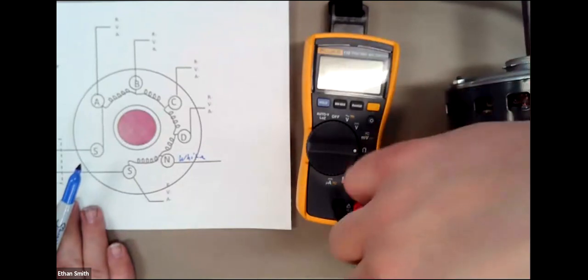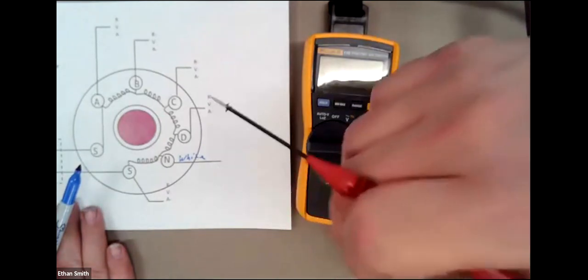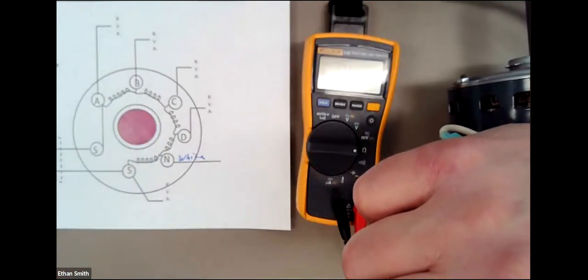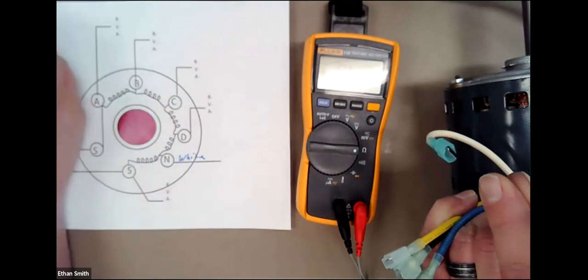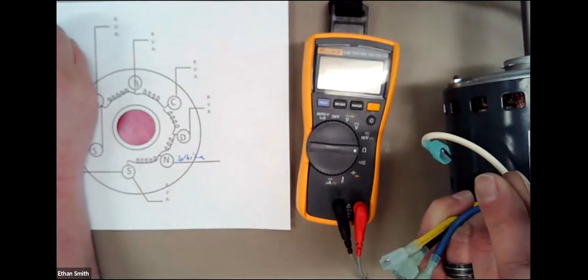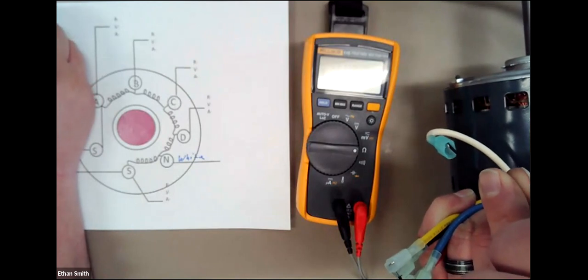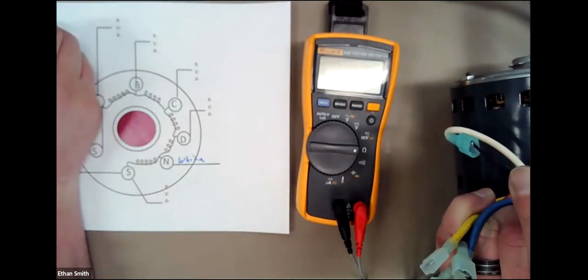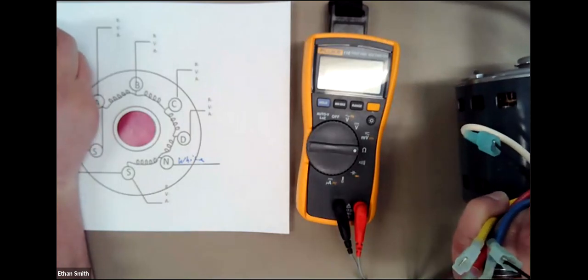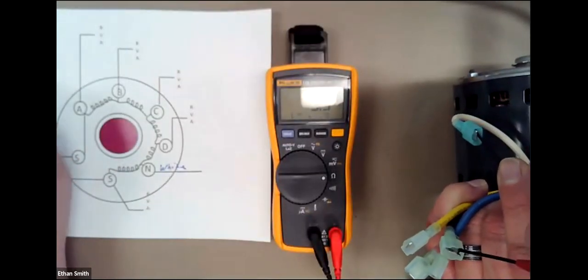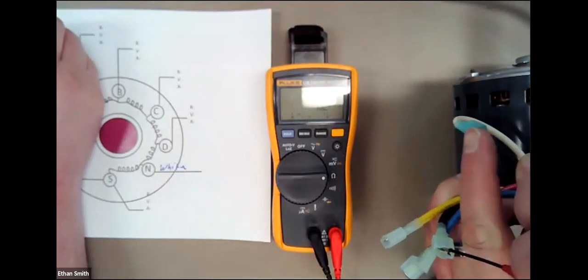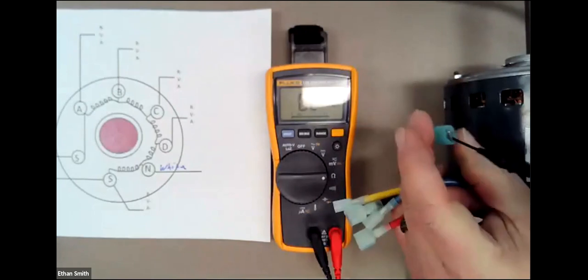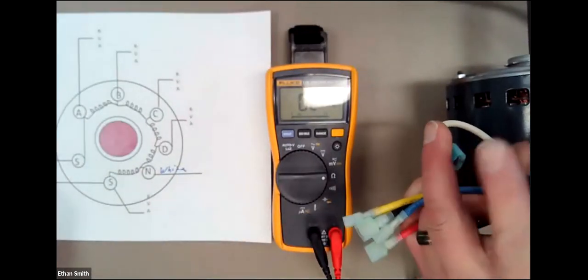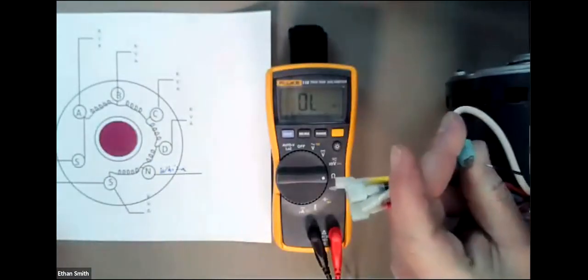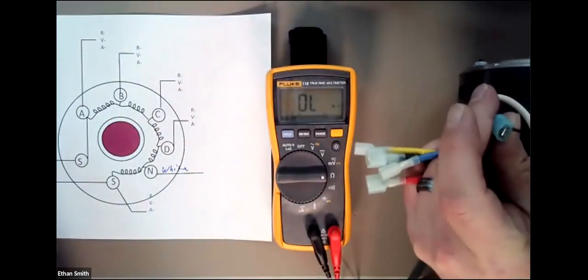Okay, so the first thing we have to do is find a wire that gives us a resistance. Because I don't have any colors labeled here, we're just going to pick one, and I'm going to write the resistance values down here. Which one are you on, Keith? I can go to black. So this is white to black. That gives us, according to the meter, which you're getting glare on, 3.5. Sean, can I get you to turn the perimeter lights off? See if we can get the glare on the meter to go down, so they can actually see it. There we go. So white to black was 3.5.